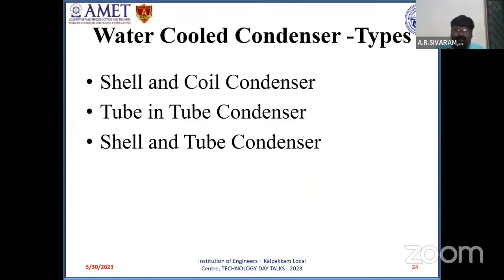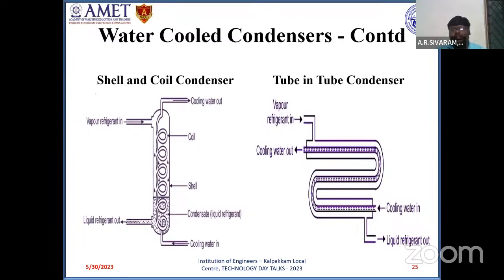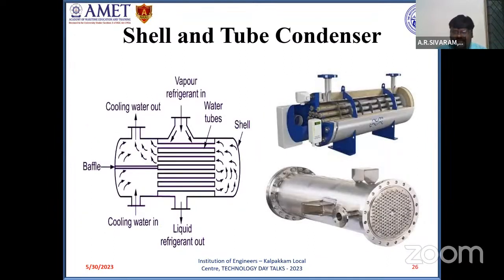And coming to the water cooled condenser, it is normally of three types: shell and coil, tube in tube, and shell and tube. Shell and coil is preferred up to 50 tons, and this has one single shell. Usually water flows inside the tube and refrigerant flows inside the shell. In tube in tube, refrigerant flows in one tube and water flows in the other tube. The last one is the shell and tube condenser. For very large refrigeration systems, and for commercial and industrial refrigeration systems, shell and tube condensers are employed.